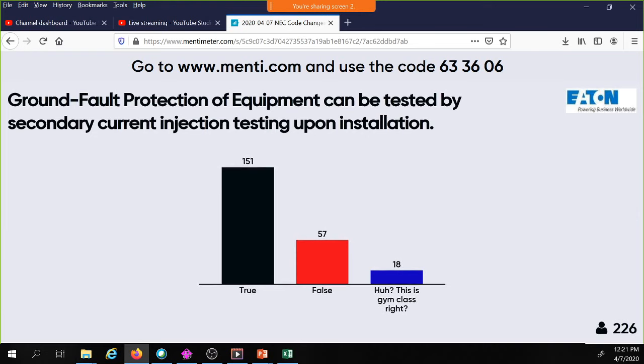Ground fault protection of equipment can be tested by secondary current injection testing upon installation. 151 say true, 57 say false. Now, this is a 2020 code version class. I don't have my 2017 book, but guys and gals, secondary current injection testing became illegal for GFPE testing in the 17 code. You have to do primary current injection testing. That is a must. That was a Code Making Panel 10 decision, and that is why I put it there. I put that in there because that is what drove Code Making Panel 10 to beg the question on why we don't have field testing of our arc reduction technologies when we require performance testing in 230.95.